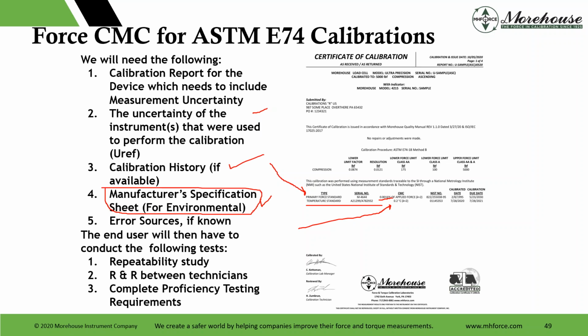Error sources if known, and then we say the end user is going to have to do a repeatability study, R&R between technicians. And if you're accredited, you're going to have a program to complete proficiency testing requirements. This is where if you buy that second load cell, like a mid-range, you can do a lot of stuff with that second load cell. You can use it for ILCs. You can use it as a check standard.